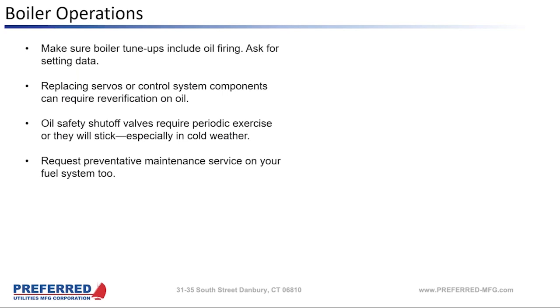Something else I experienced was sticky oil safety shutoff valves. If you don't use these safety shutoffs after a while, the valves will stick and they won't open. And the Cadillac in oil safety shutoff valves is the Maxon valves, but they're susceptible to this. I've had Maxon valves where the little gate in there gets all gummed up with oil when it's not being used, and that kind of glues the oil valve shut, and the actuator can't overcome that glue. So it's important to exercise your oil valves every once in a while by running the burner on oil a little bit. At least light it off and exercise the valves a little bit.